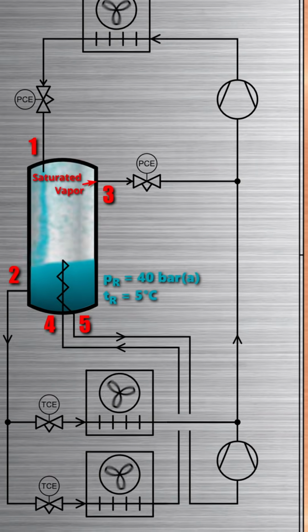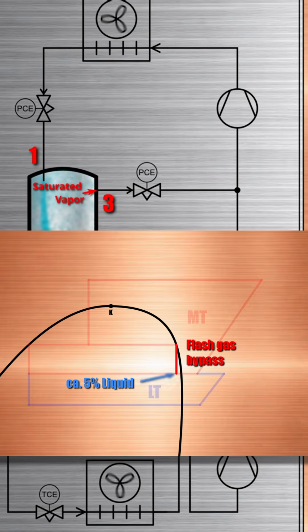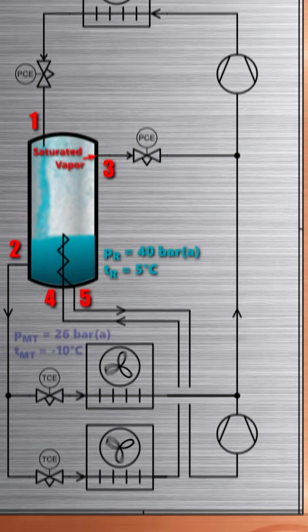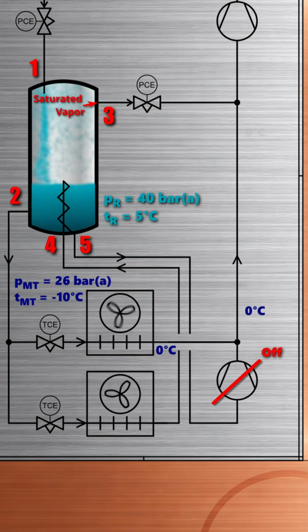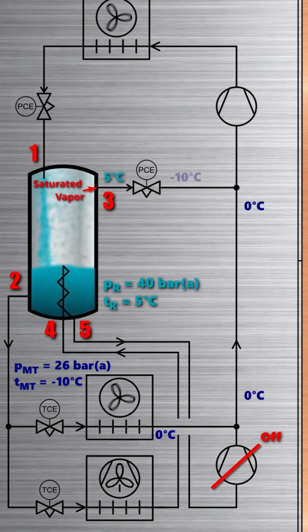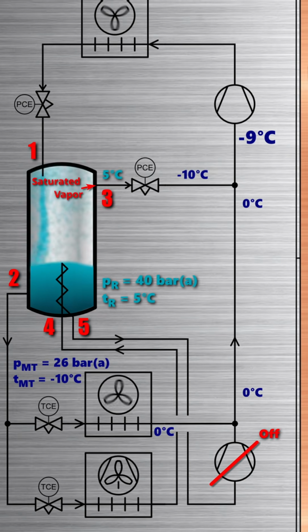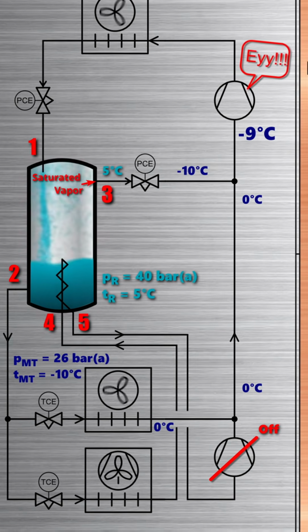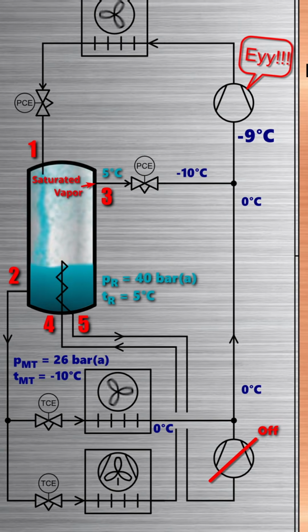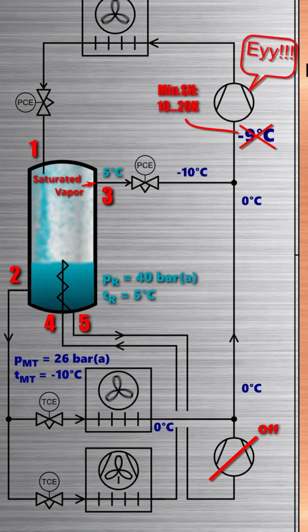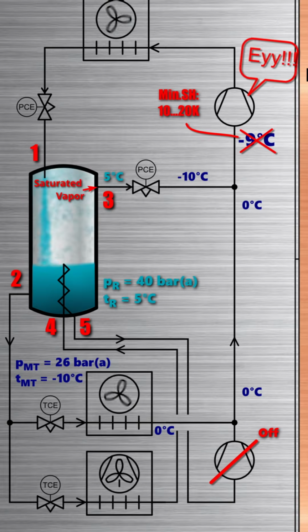The throttling of saturated vapor produces a small amount of liquid. If the combined suction line goes straight into the medium temp compressor, liquid carryover can quickly reduce superheat and cause lubrication issues. The medium temp compressor requires nearly the same superheat conditions as the low temp compressor.